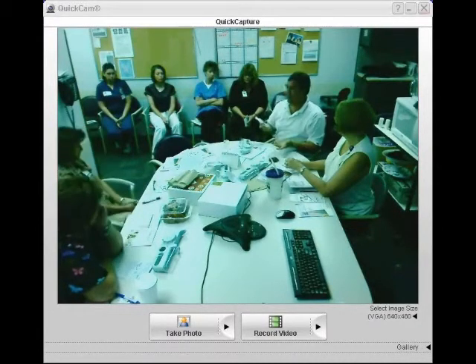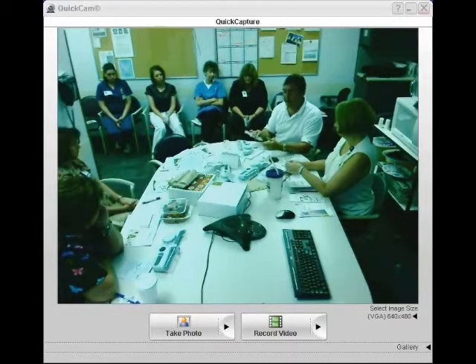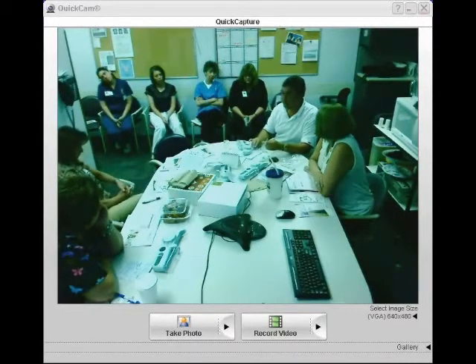All right, I'm just going to connect this. This is a 2-site set, so I'm going to put 30 mLs into my syringe, so I kind of cheated a little bit. We're just going to then insert that after we've got it all primed. You go ahead and insert your needles at that point, or you go ahead and load your syringe into the driver? Nope. I go ahead and insert the needles because you want to check for a blood return before you put the syringe in the pump.